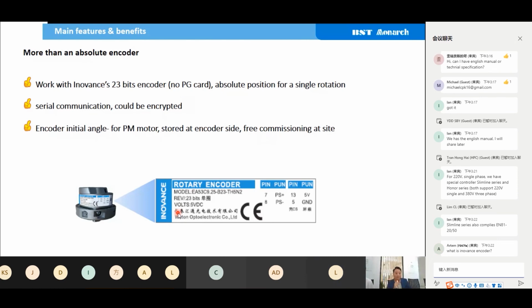And the last and most important point: we store the encoded data at the encoder side. What does this mean? It means at the job site, you don't have to do the motor tuning. Once the cable is connected and powered on, the control cabinet will automatically recognize the encoded data from the encoder.